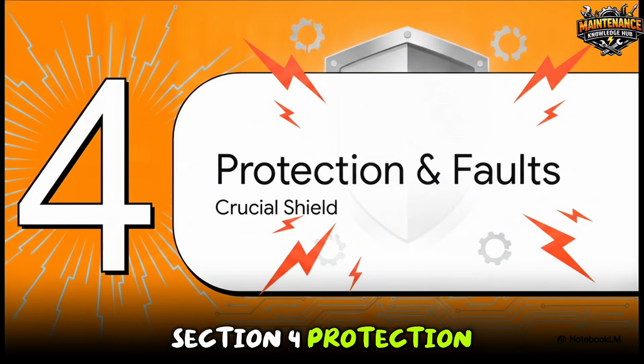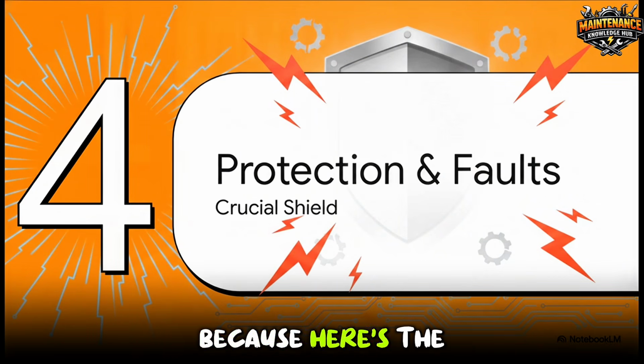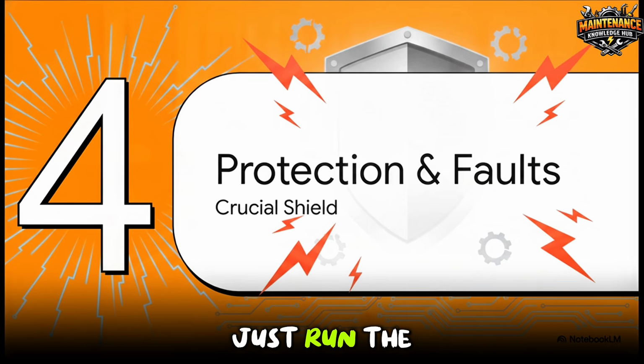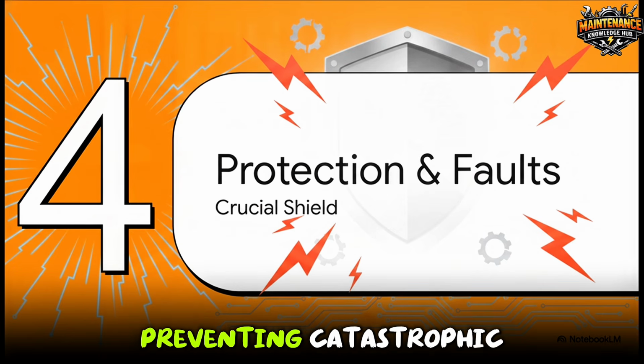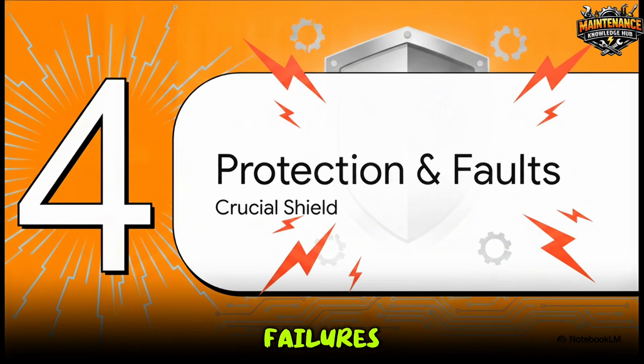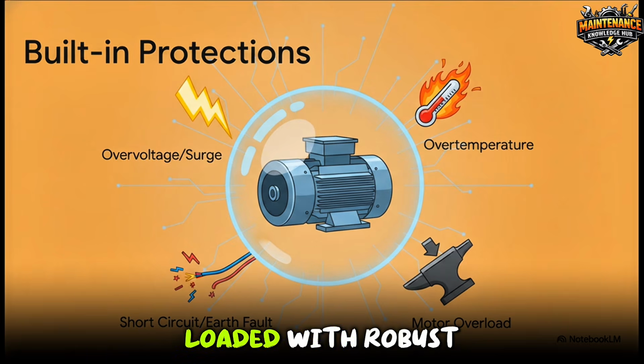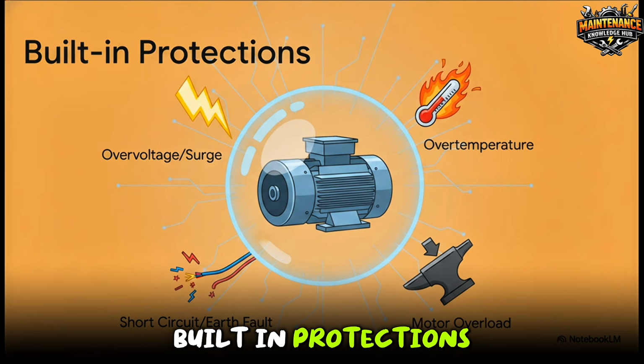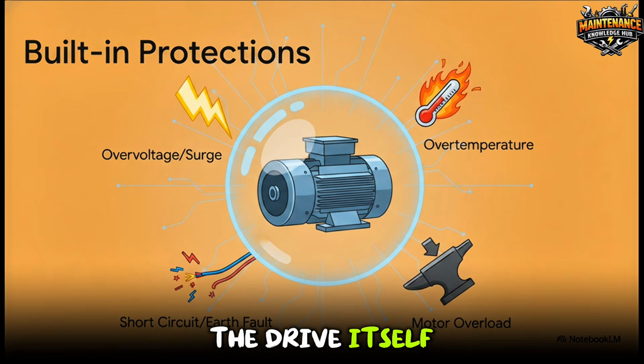Section 4. Protection and faults. Because here's the thing, VFDs don't just run the motor. They also act as an absolutely crucial shield, preventing catastrophic electrical and mechanical failures from destroying your entire system.